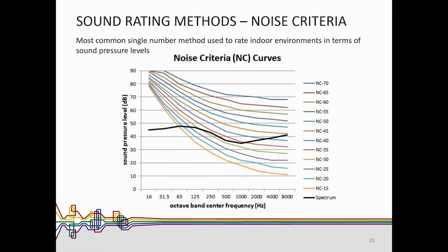Now there's a variant of this that I'll just touch on for a second, which is called RC, or room criteria. That's supposed to help us characterize in the HVAC world whether it's a hissy kind of sound or a rumbly kind of sound, or it's likely to be irritating. But that's not part of B3, and it's really just one of those things that when you go to the ASHRAE handbook, it's on page whatever, and it tells you how to do it, and even if you calculated it, you wouldn't know what to do with it, who to give it to, or what they would do with it anyway. So those are kind of the common rating systems that we would have.